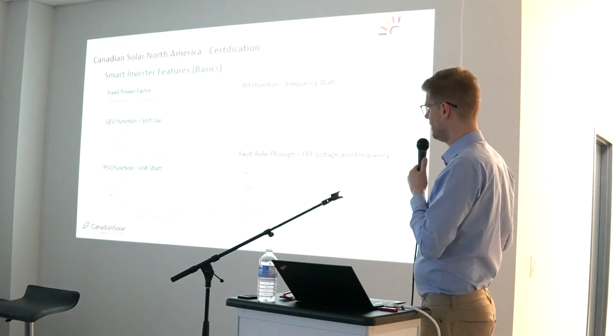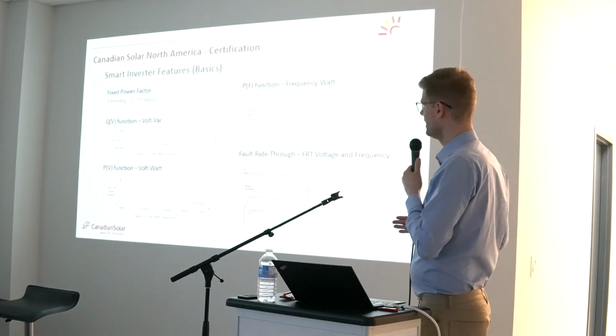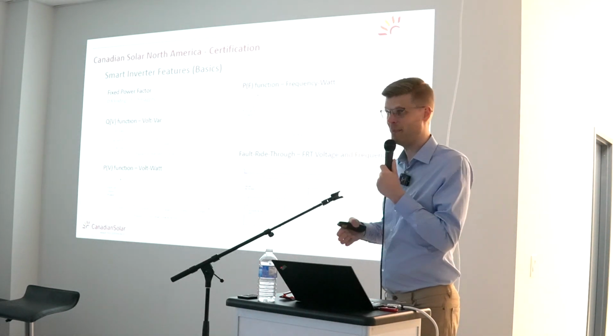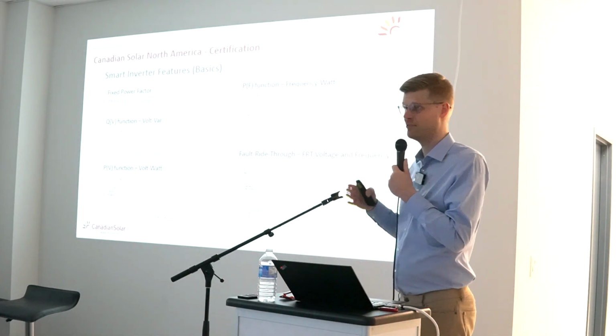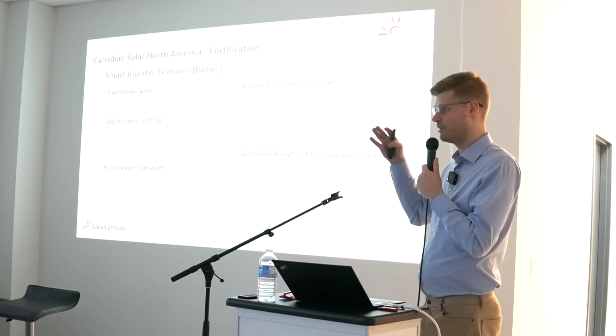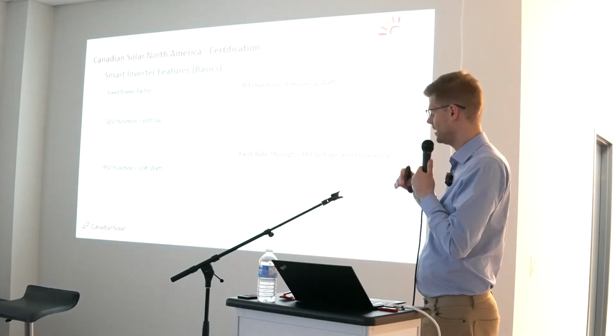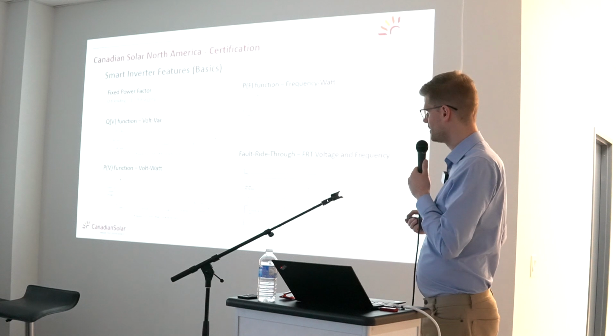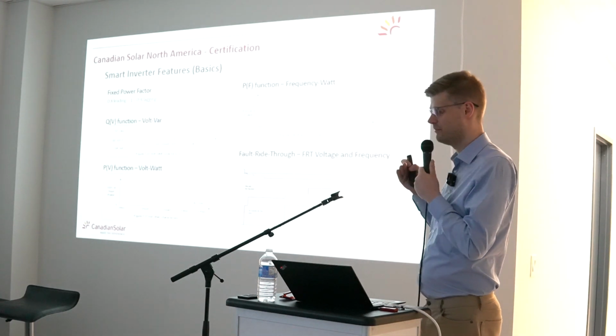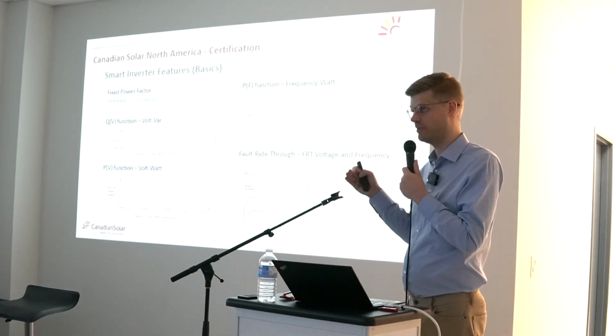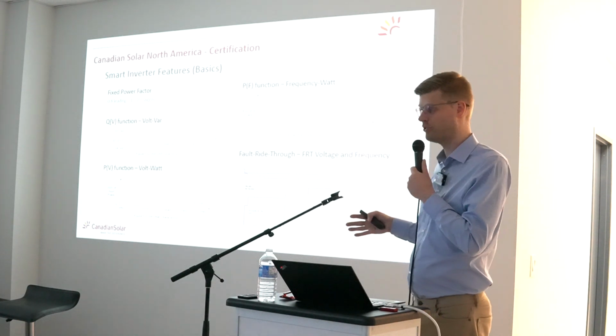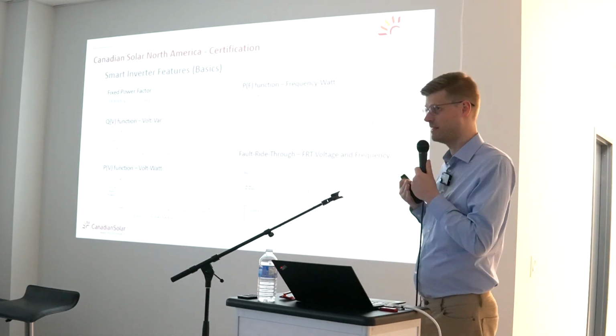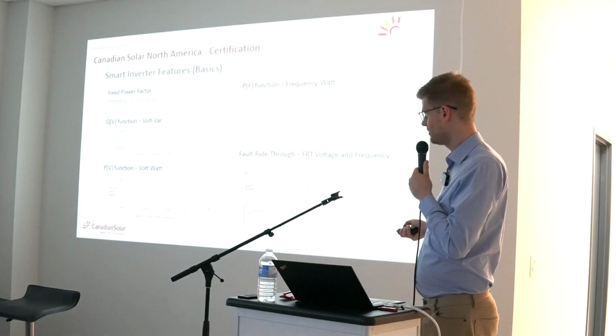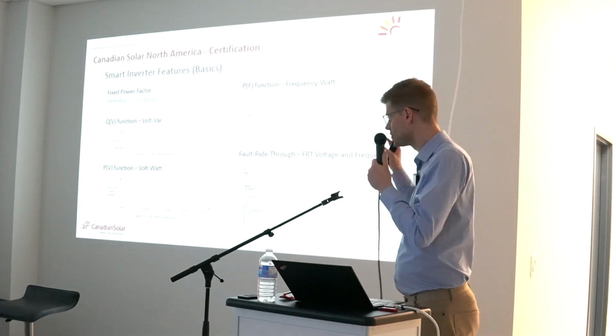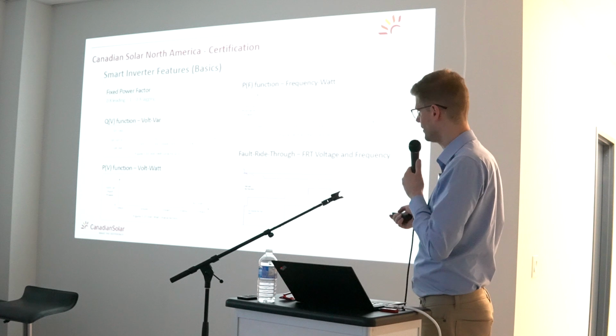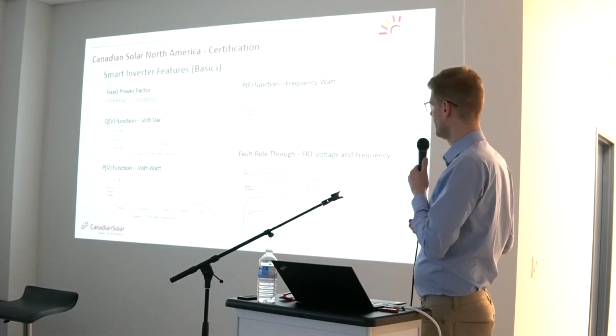Fault ride-through is a very big topic. In the past, the inverter had to stop immediately if there was a grid fault and the frequency or the voltage went out of spec, so overvoltage, undervoltage, and overfrequency, underfrequency. A new requirement came in requiring the inverter to stay on the grid for a certain amount of time to participate in fault clearance. So instead of shutting off immediately, it stays on the grid for quite some time depending on the conditions, and that's the window of operation until it has to shut down.